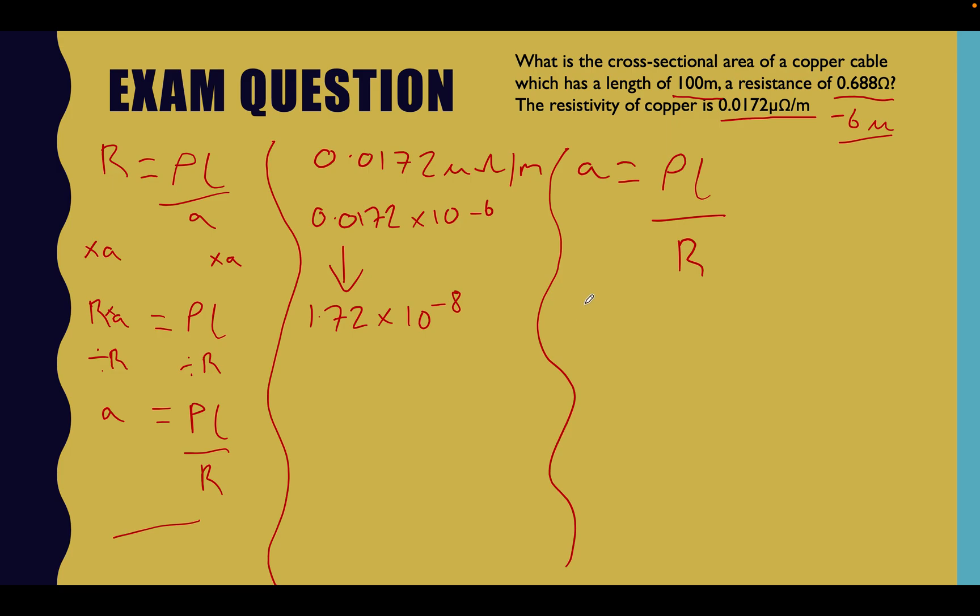Right, let's put some values in. So the cross-sectional area is going to be equal to 0.0172 times 10 to the minus 6 multiplied by the length, which in our case here is 100 meters. So that's multiplied by 100. And then we're going to divide all this by the resistance reading that we've got to deal with, which is 0.688 ohms.